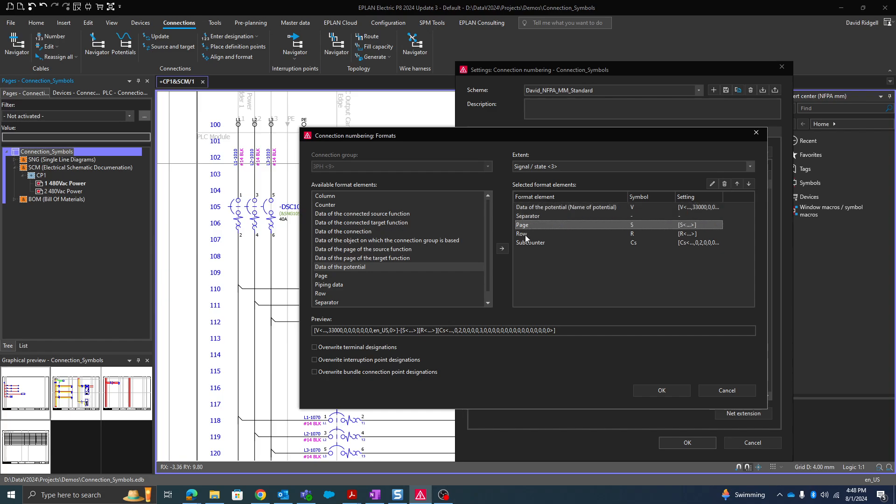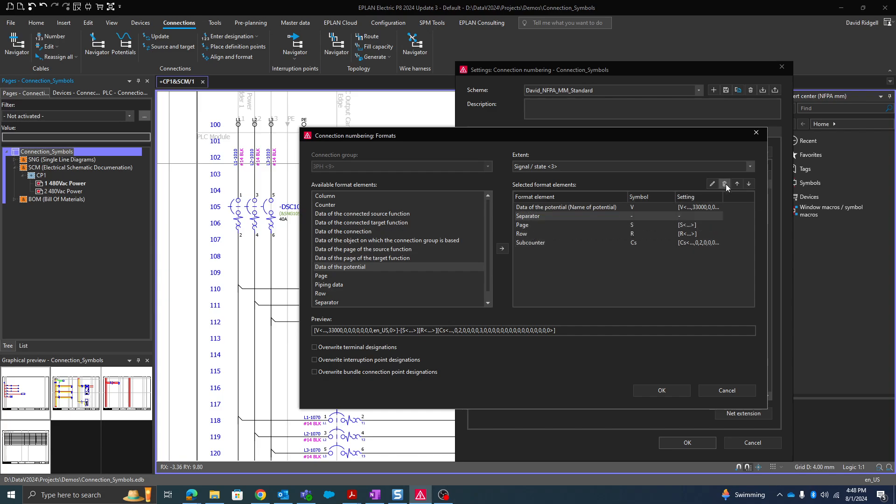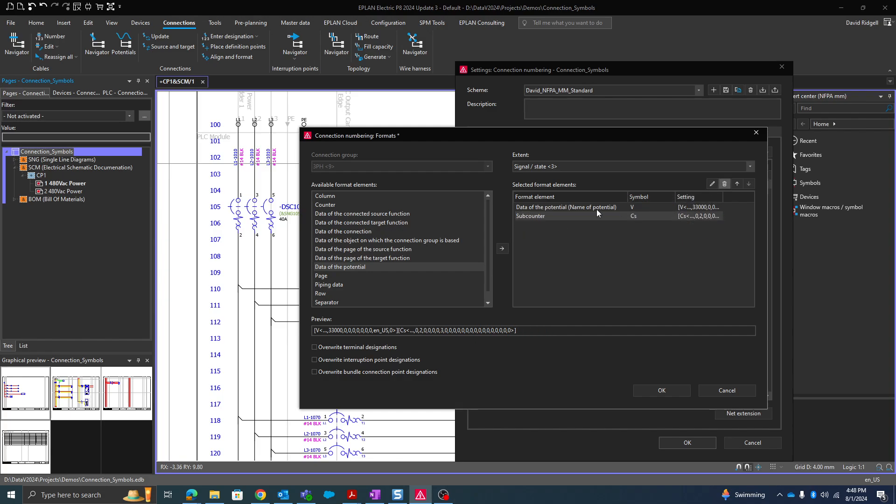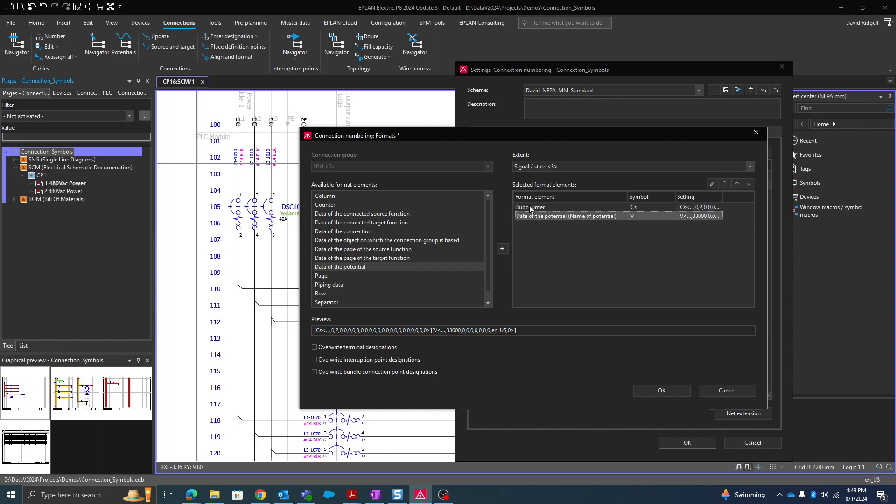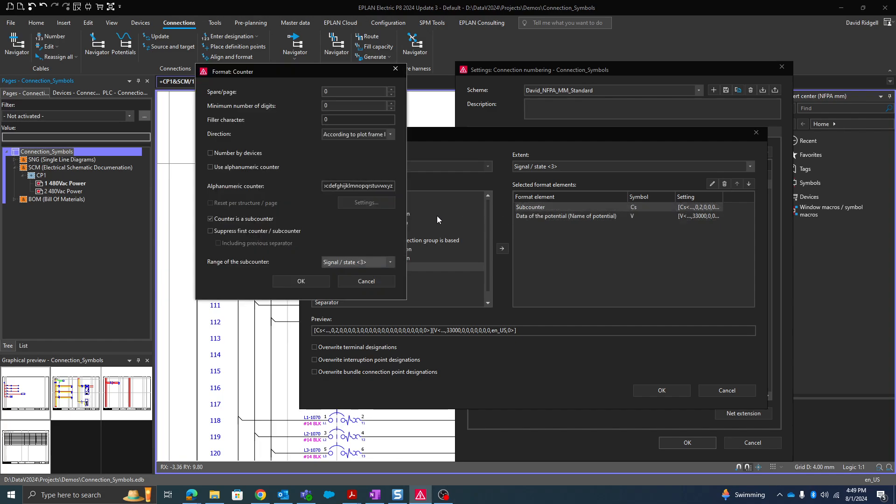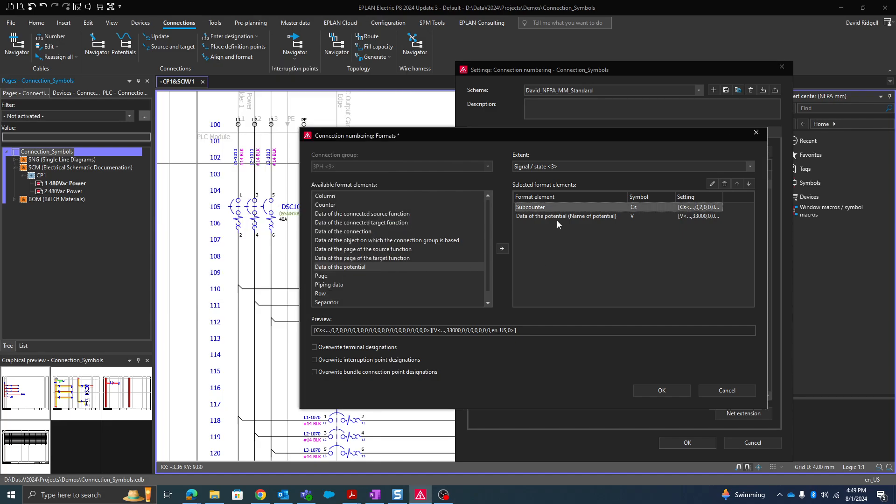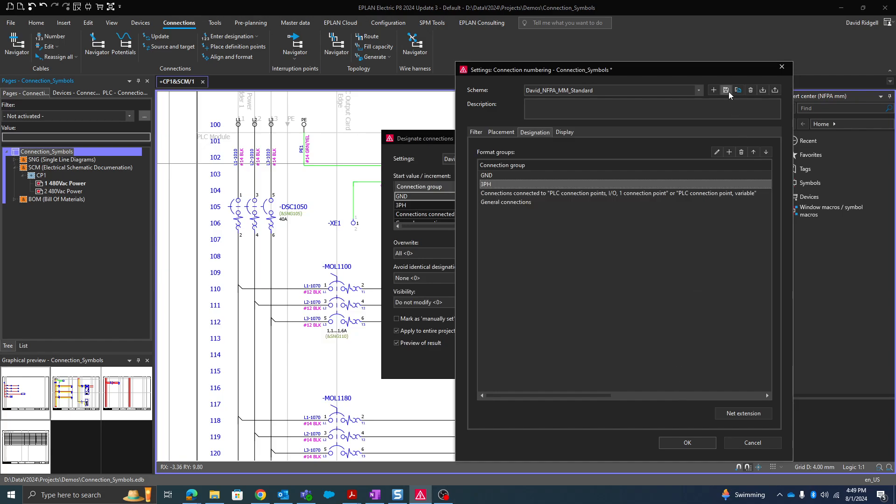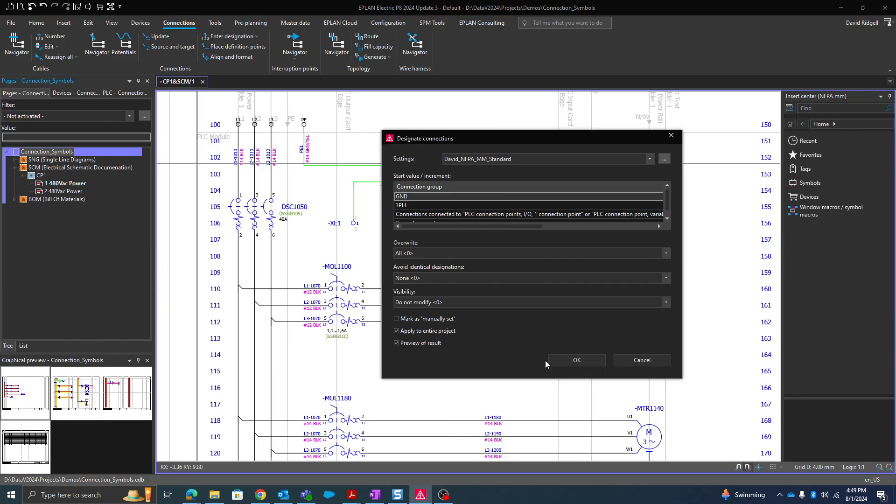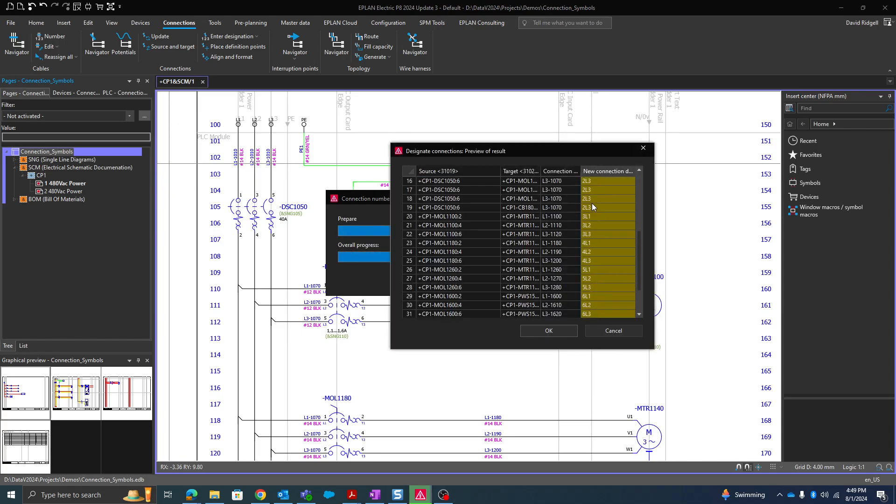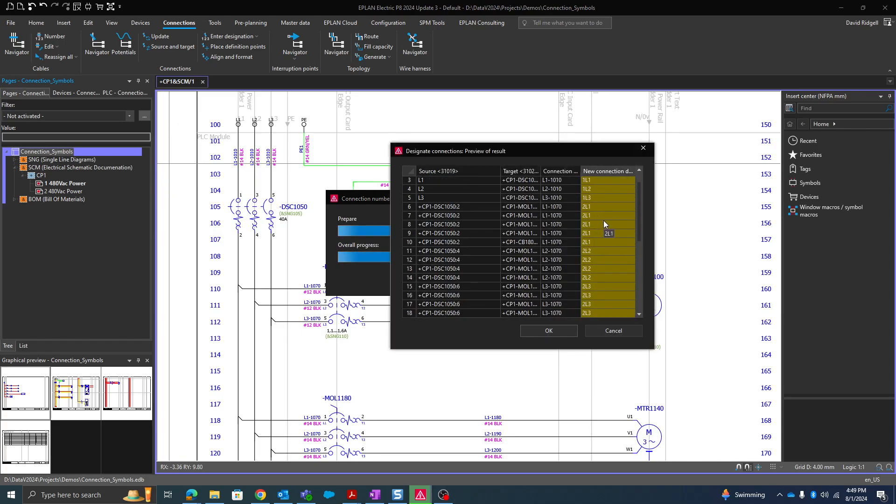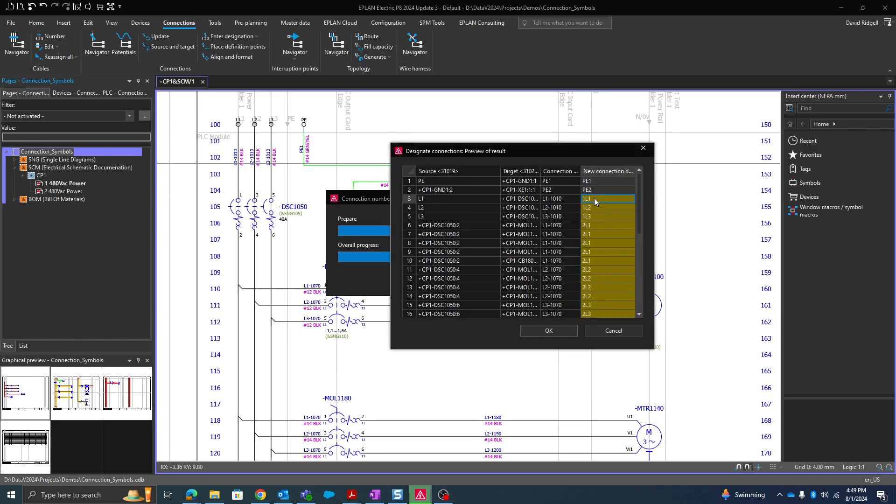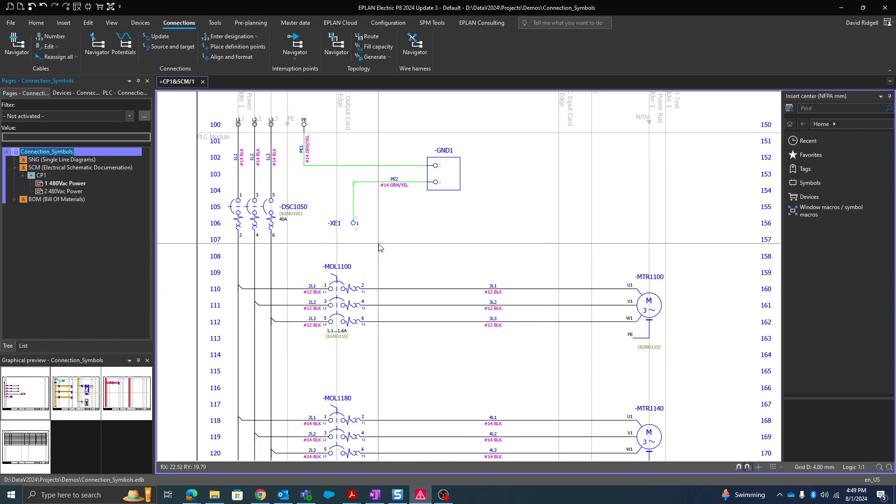I'm going to make this a little bit different. So I'm going to delete everything except the subcounter and the name of the potential. And I just want to look at the subcounter's property. So I'm fine, I'll leave that the way it is. And I'm going to save and hit OK and then I'm going to renumber everything. Now you can see I'm following the scheme 1L1, 2L1, and so on and so forth. And now we're using also potentials to control our different wire numberings.